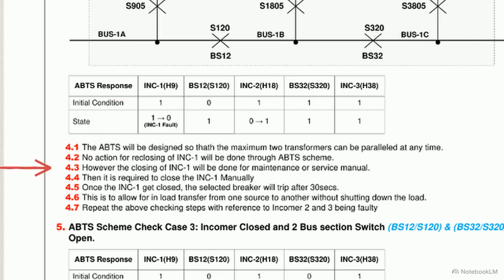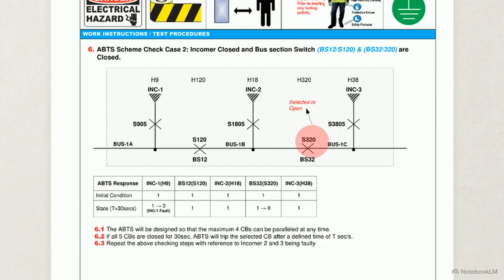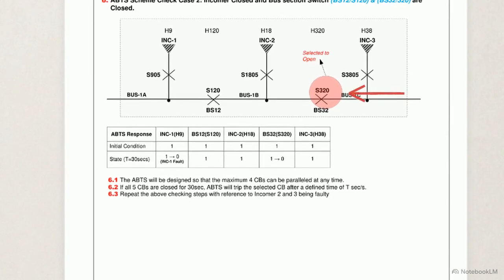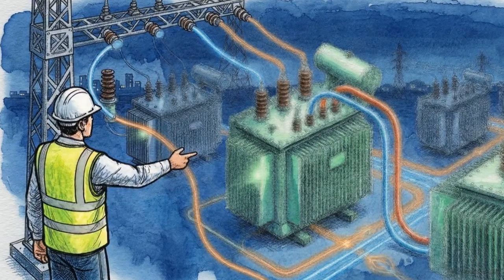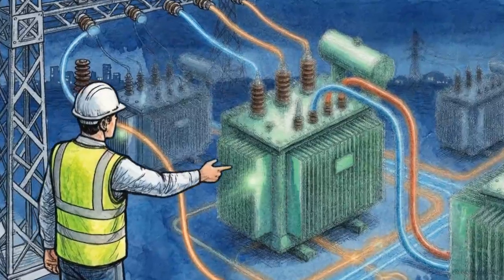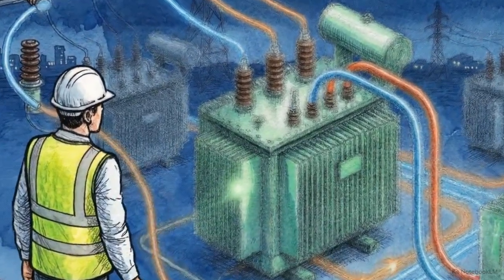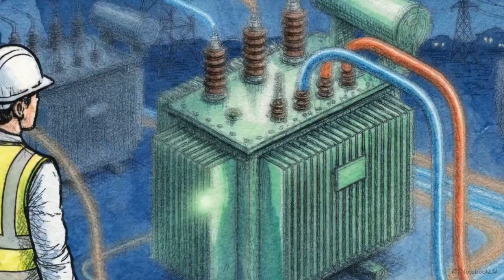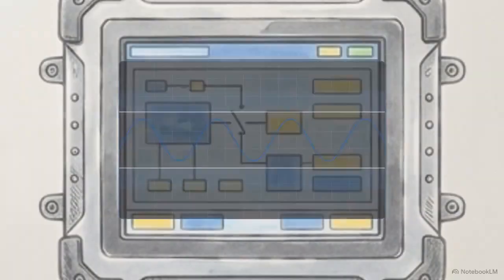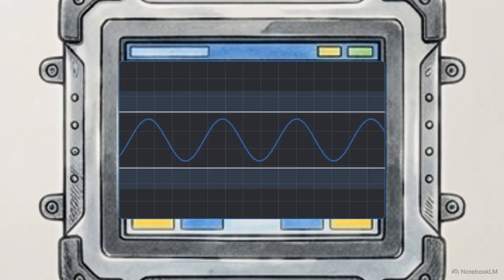or dynamically blocked. This Case 2 diagram presents a critical edge case where all bus sections are initially closed, maximizing parallel capacity. Notice the highlighted switch S320. If 5 breakers remain closed for 30 seconds, the system recognizes a safety violation, automatically tripping. Verifying these precise time delays and blocking actions guarantees that the grid can safely manage complex power transfer events, preventing massive cascading overloads. Next, we test the Automatic Capacitor Control Scheme, or ACCS.